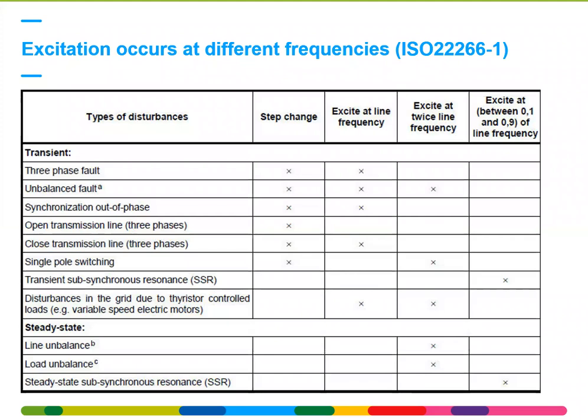So that's typically okay. The last column, however, excitation in between 0.1 and 0.9, where you have, for instance, subsynchronous resonance, there you have phenomena where you have interaction with the grid, where you can reach unstable regimes and drive the system, your mechanical system, into resonance. Those are the most important ones.